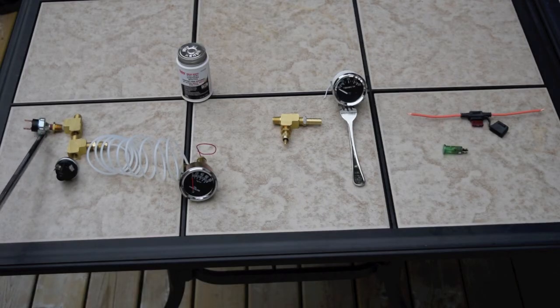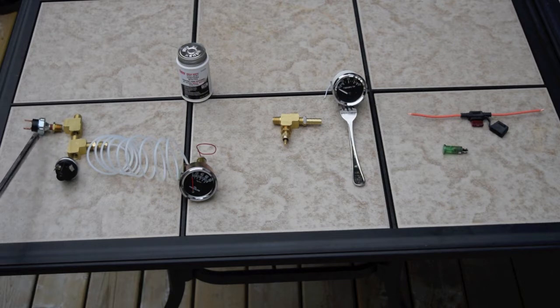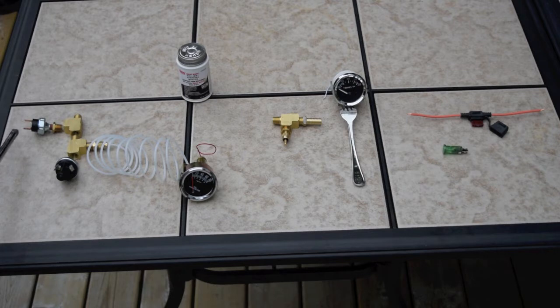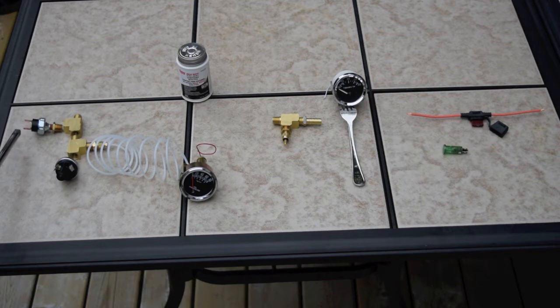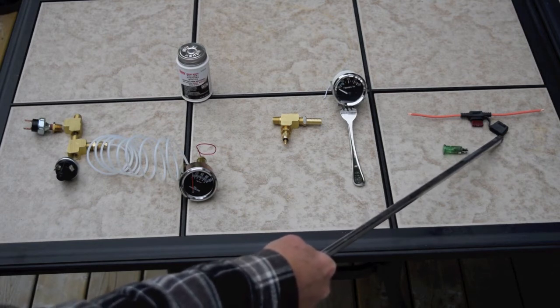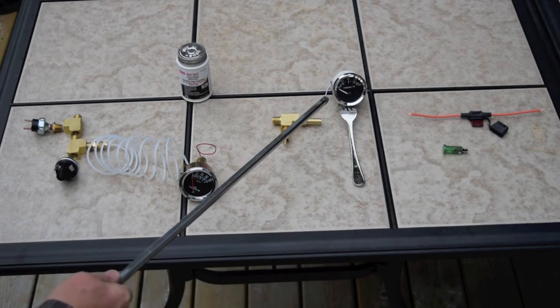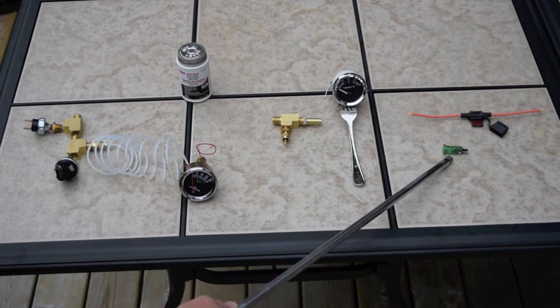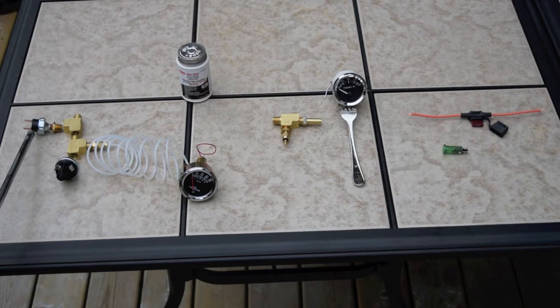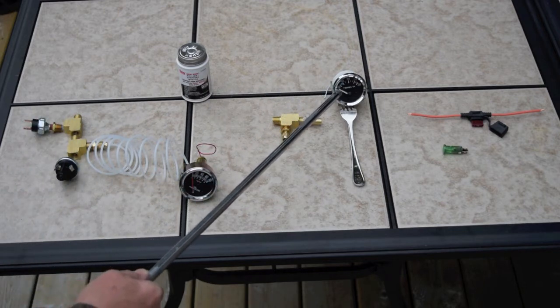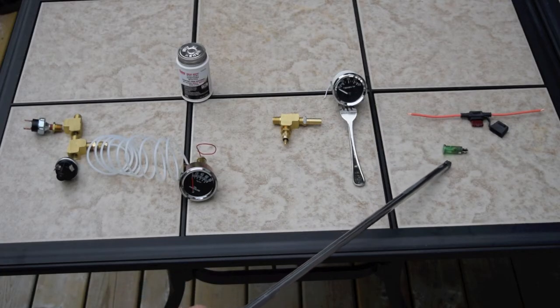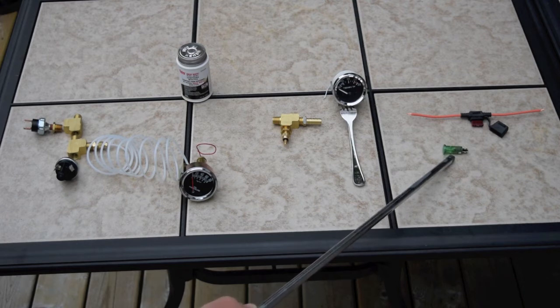This is your line out to the oil pressure gauge. This sending unit over here is a normally open oil pressure sending unit, so when the pressure comes up it will close the circuit in there, and I'm going to use that for 12 volt off of my battery. It's going to be that inline fuse there hooked to the positive, so I'm going to use the power for that. You need 12 volt to run the temperature switch and I'm also going to use 12 volt for this switch. So what's going to happen is when the oil pressure comes up, the switch is going to close. It's going to send 12 volts to the oil temperature gauge and it's also going to send 12 volts to this indicator lamp which I will have on the outside of the enclosure.